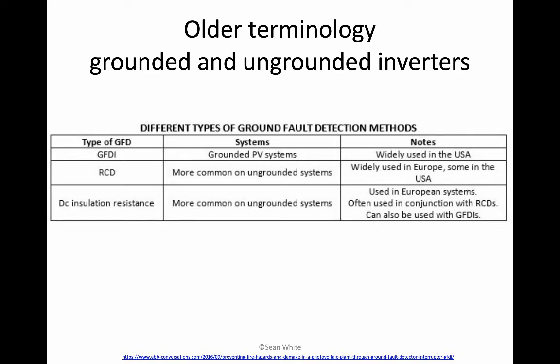Some people think it's too good at finding ground faults, and when they replace an old inverter with a new inverter, they can't get it to turn on because it's always finding a ground fault, because there's just a little bit of leakage going through the insulation of that wire. So when something like that does happen, usually what they'll end up having to do, if they can't find the ground fault, is just get into the inverter with a computer and change the settings a little bit so it's not so sensitive.